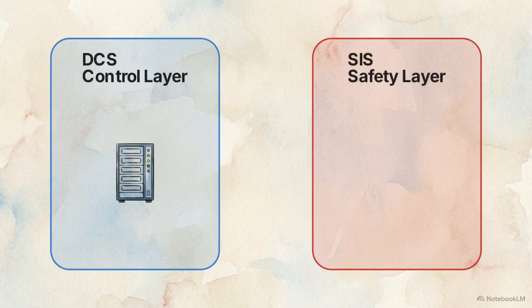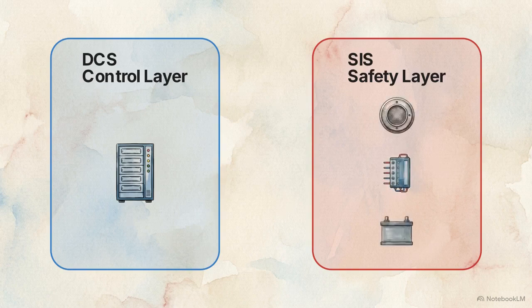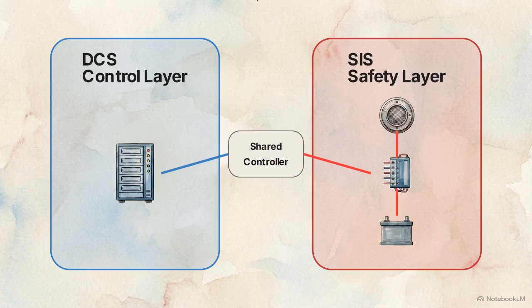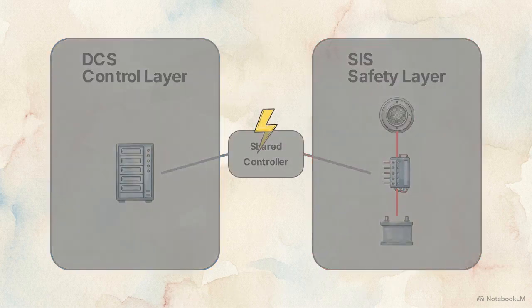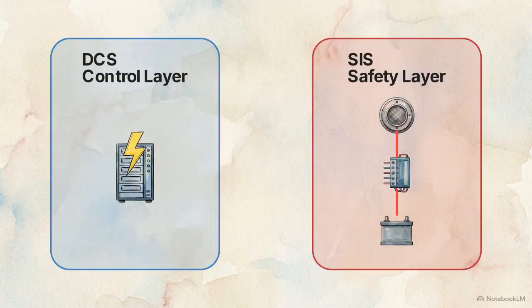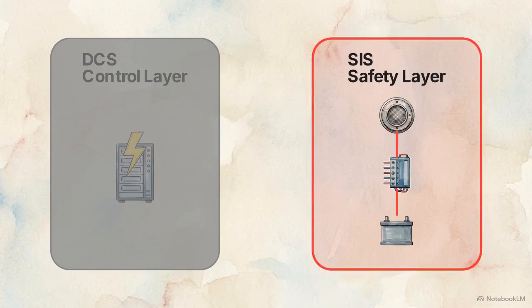This diagram illustrates the defining engineering axiom of process safety. The SIS must remain physically and architecturally independent from the DCS. The safety system utilizes its own dedicated physical sensors, logic solvers, copper wiring, and power supplies. If the control and safety networks operated on the same hardware controller, a single fault would destroy the process regulation and the emergency failsafe simultaneously. The independent architecture guarantees the safety system survives the failure of the control system.